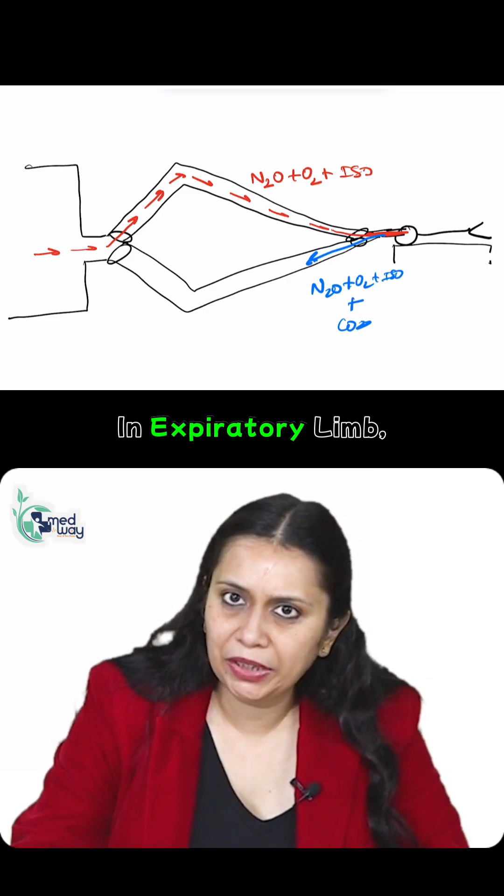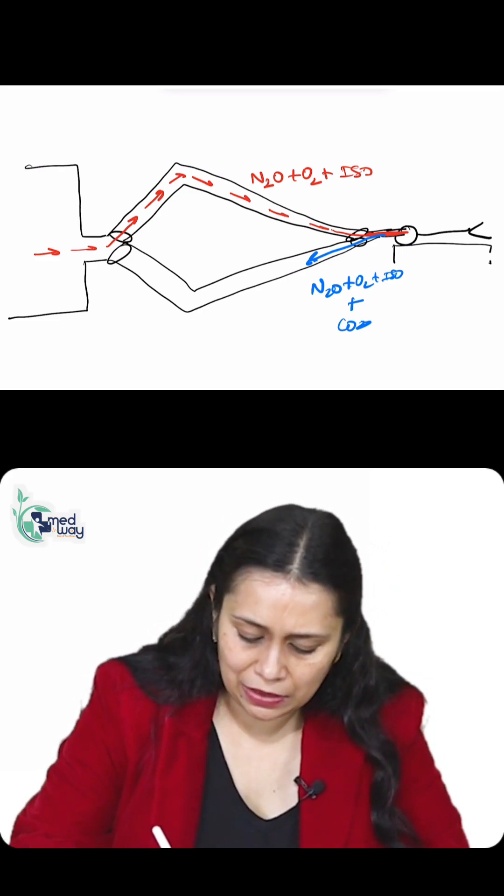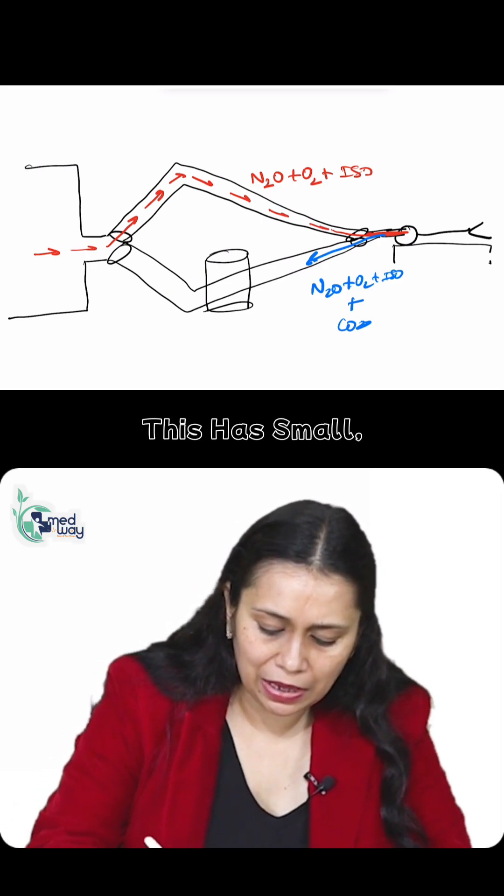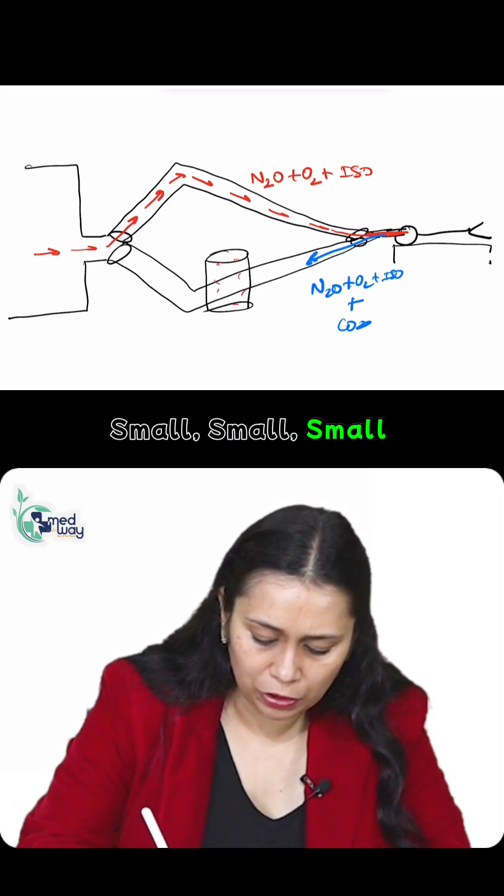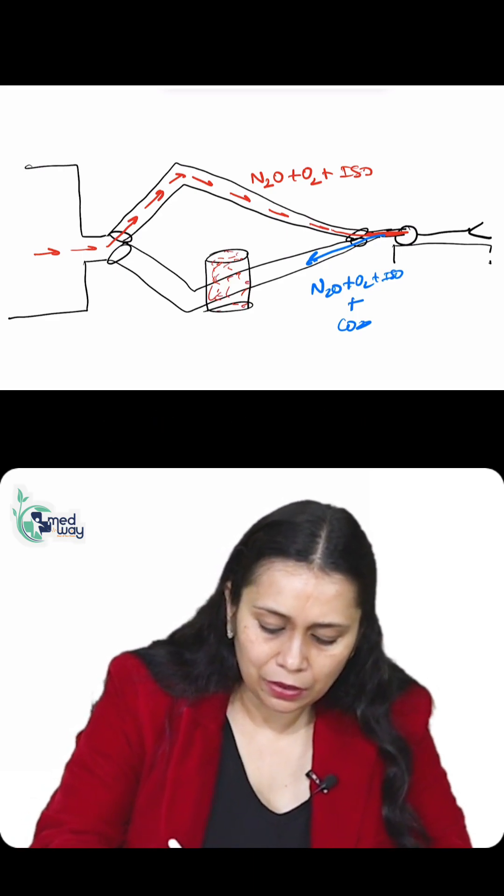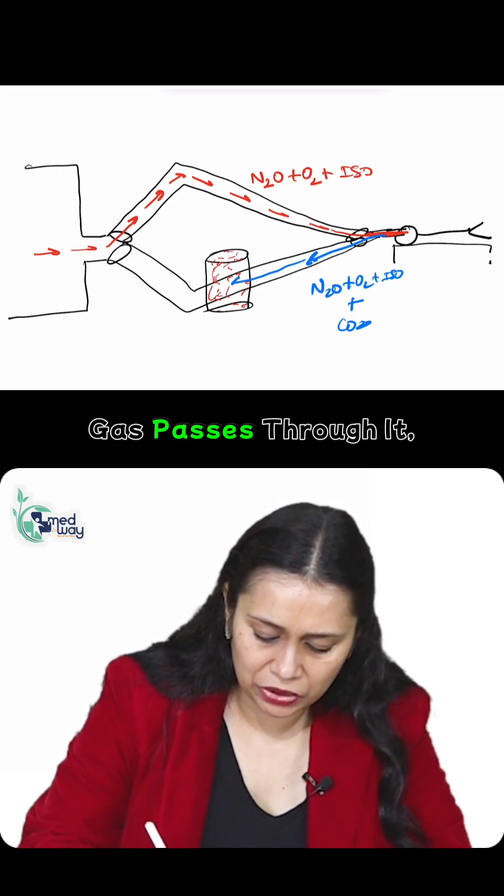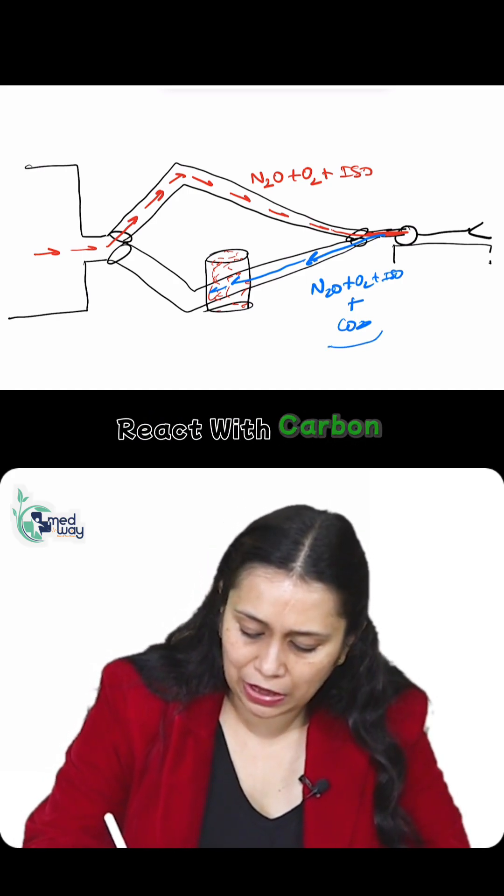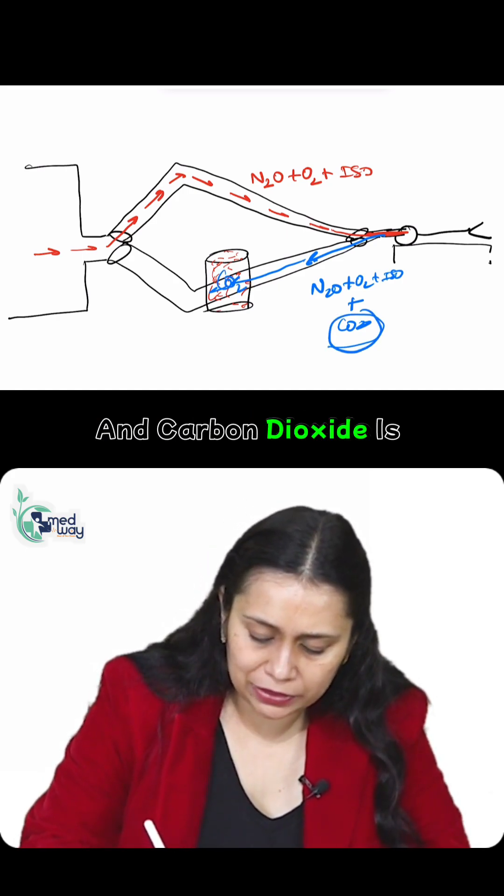In the expiratory limb, a very important new component was added called the carbon dioxide absorber. This has small granules present in it, made up of chemical substance. When the expiratory gas passes through it, the chemical present in these granules reacts with carbon dioxide, and carbon dioxide is absorbed.